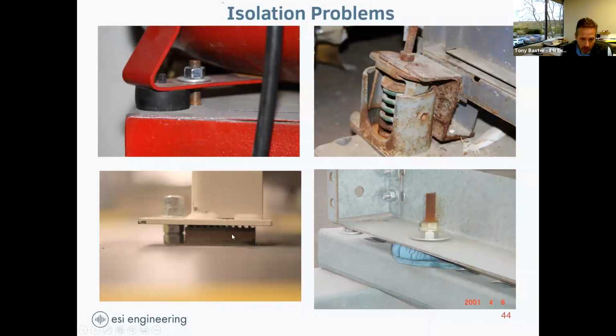And here in the lower left as well, we've got some cork and rubber pad, but they put four nuts on that one. The forces go straight to the stiff point—this pad isn't doing anything. It's surprising to go into buildings, have them complain about vibration or noise, and find isolators in this condition.